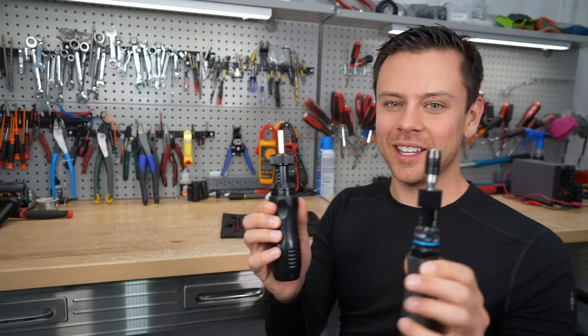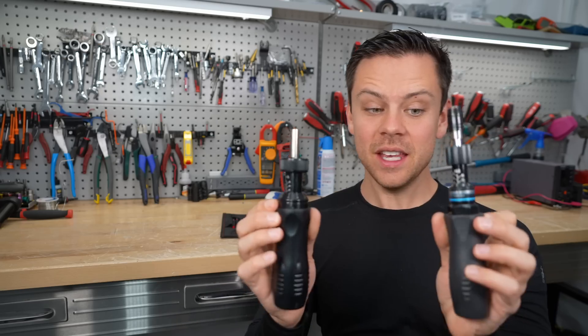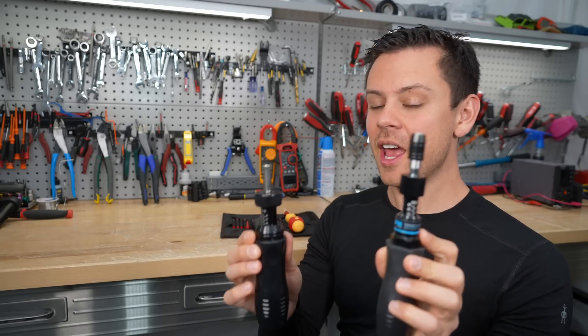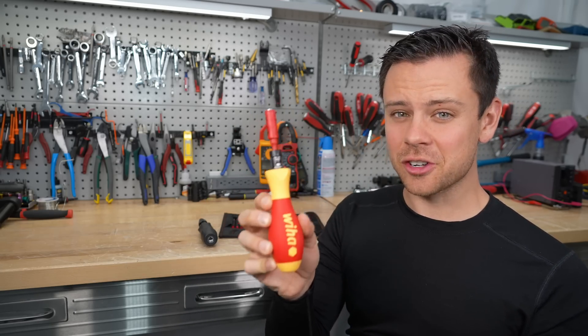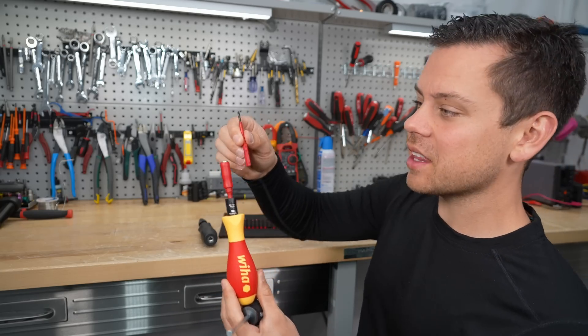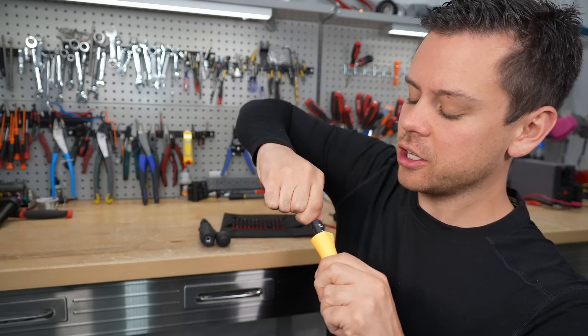First we have torque screwdrivers. If you have a torque spec on a terminal, you need to use one of these devices. These are some budget ones — the Capri is probably my favorite budget one. But if you spend more money, you can get the Wiha, which is electrically insulated. It costs more, but it comes with bits that fit really nicely on electrical terminals. It's quite different than the others on the market, so let me show you how to use it.